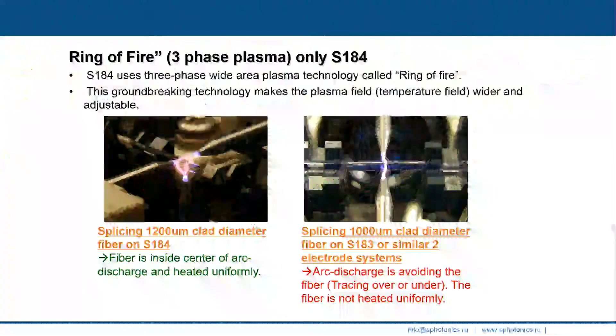The main point is that in order to splice fibers of really huge diameters, we need a really big, uniformly heated area, and you can't make it with just two electrodes. So our American partners use three electrodes. Actually, it is just ground and two phases. This allows using one splicing machine not only to splice fibers of small diameter, specialty fibers like PCF fibers and polarization maintaining fibers, but fibers of really huge diameters as well. This is really useful for labs, for lab equipment. It is a really nice solution.